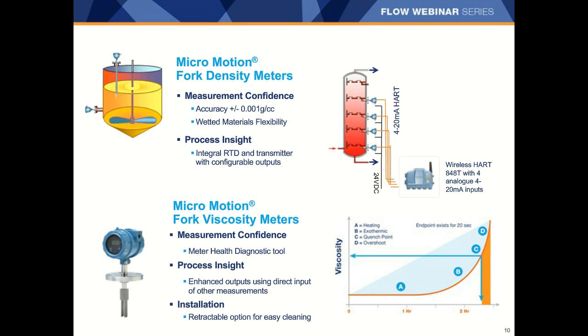Here's a topic that we don't talk about very much. So let's take a look at fork meters. A lot of our customers use the Coriolis technology as a densitometer, but when you need additional measurement confidence, we have a density fork offering. The vibrating fork is inserted into the liquid to be measured, and its tines are vibrated piezoelectrically at their natural frequency, with the natural frequency of the system changing with the density of the liquid in contact with the tines, similar to the behavior of a tuning fork for those musicians in the audience.